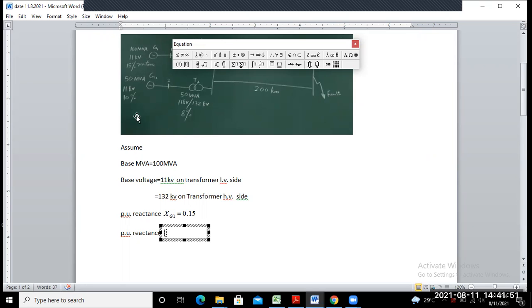That means 0.1 is your old per unit reactance value, and put in MVA new and MVA old, and kilovolt old divided by kilovolt new whole square. So just put in that and tell me what is the value of XG2. Is it clear how we can convert any existing per unit reactance value on a specified base to another base value? So per unit old is how much? 0.1, is it not? 0.1 is your old value, which is given as 10%, that means 0.1.